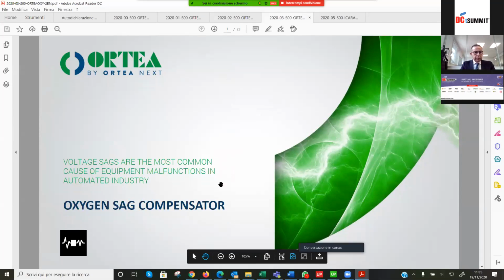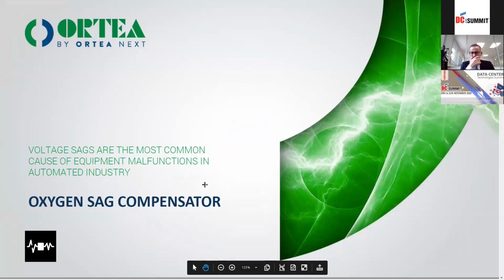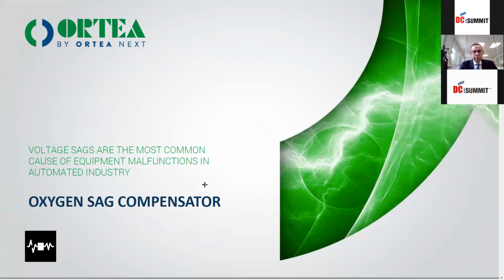Now we will see our sag compensator systems. The sag compensators are very important when you have problems on very sensitive loads, like for example producing LCD screens or pharmaceutical processes, where even if you have a small problem on the voltage side, you can have big troubles on the production lines, or even in pharmaceutical application, be obliged to stop totally the process and maybe throw away a volume of material that can cost a lot.